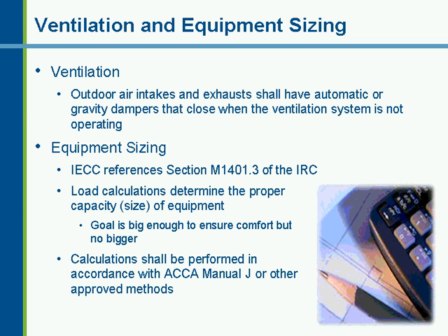When you install those, there are specific requirements for sizing your equipment properly. Those are taken from the IRC in the section noted. You must conduct those load calculations to compute the appropriate size. That may seem like an odd requirement in an energy code, but it's important to get the equipment sized correctly in order for it to operate efficiently and operate the way it's supposed to.